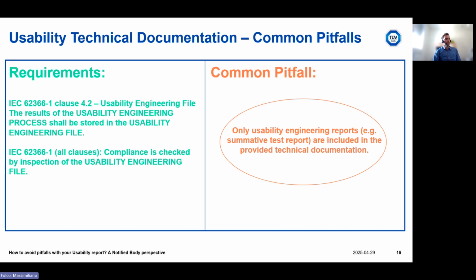Maybe the other deliverables that are required by the standards have not been properly documented. This leads to a deficiency report where the assessor has to ask, please provide us the proper usability engineering file and the proper deliverables required by the IEC 62366, that is the state-of-the-art standard.